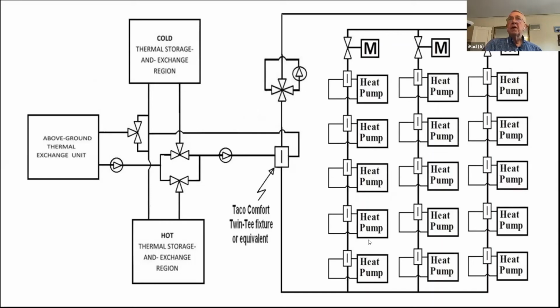Now, the purpose of this reversing valve, getting back to that, is this: if we do not have a reversible flow capability, and we have clockwise flow in what's called the primary loop, where my mouse is going now, and the heat pumps each have their own small secondary loops, then if the water is always flowing clockwise in the primary loop, the 3 heat pumps at the top in this design will always have the very best temperature and the highest efficiency, and also heat and thermal capacity.